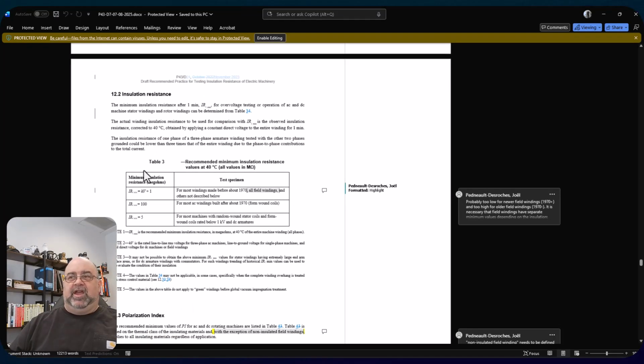This is the big question, right? For windings made before 1970, and all field windings, and others not described below, 1 kilovolt plus 1 megohm per kilovolt. So 1 megohm plus 1 megohm per kilovolt. So a 480 volt motor would be 1.5. Now, here's what's really important about this. Temperature corrected to 40 degrees centigrade.